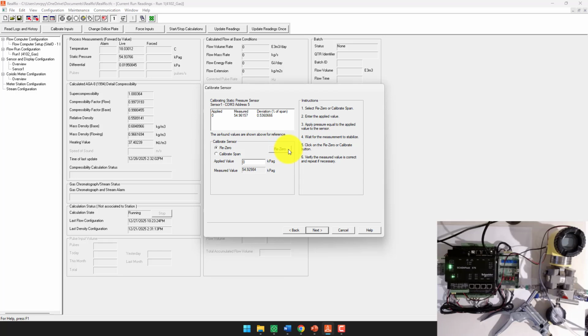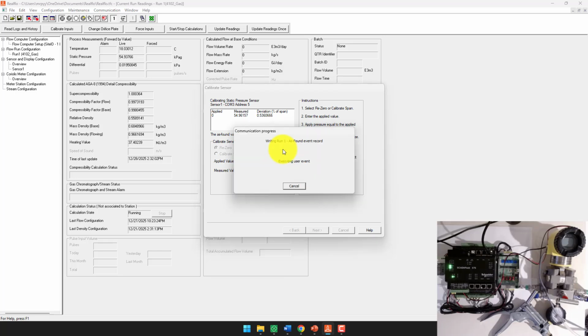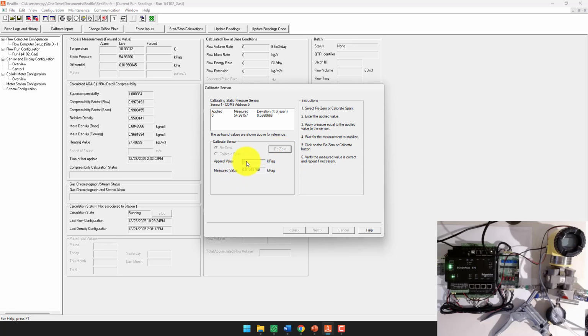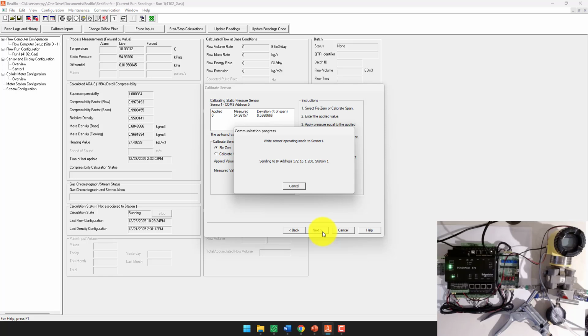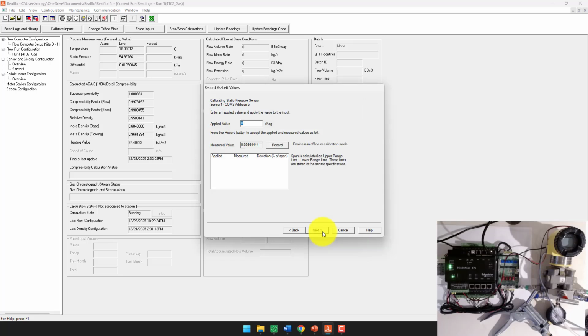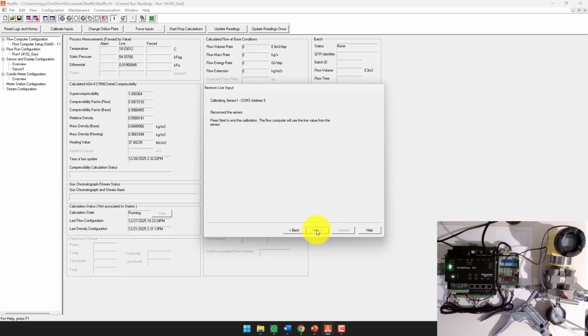And now we're going to pick re-zero. So now we're reading right on 0. Now that's done, we can select next. And then we will record this again. Now you can see the applied value and the measured values are quite a lot closer than last time. Hit next. And then now you could go ahead and reconnect the sensor, because as soon as you hit next, it's going to pull the force values off.